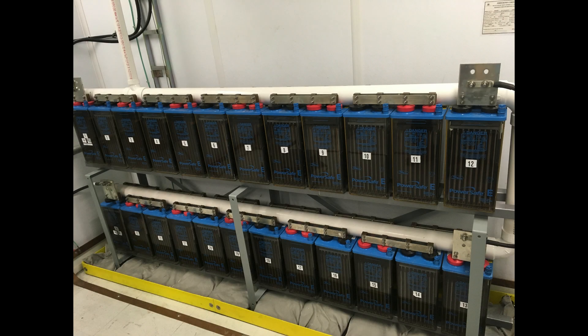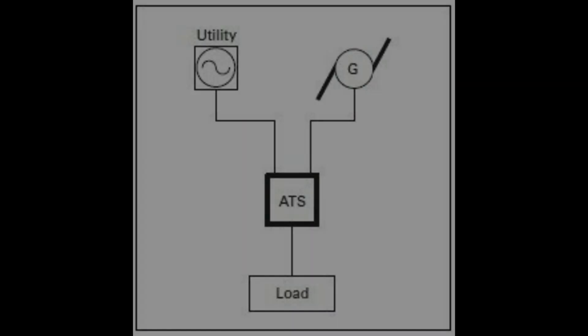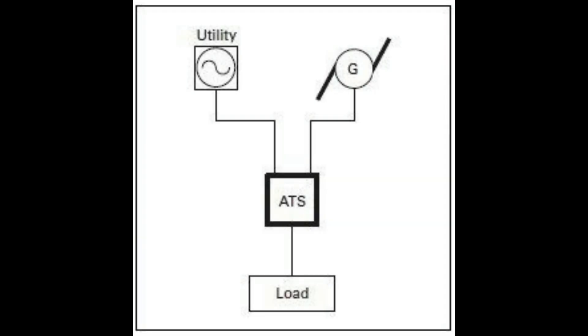It's helpful to think of a fuel cell as a DC generator, since its output voltage is a DC voltage. As such, it's connected directly to the battery bus. Because of this, unlike an AC generator, there is no need for an AC transfer switch. The AC transfer switch is used to switch between two input sources — either the public utility AC power grid or the output of the generator. Transfer switches are another point of failure, as well as an added expense.